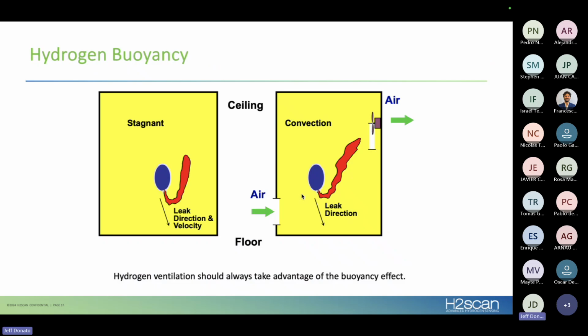We also have to watch where we place sensors. This is, I should say, not an application specific slide. With anything that's leaking hydrogen or creating hydrogen, we have to worry about the hydrogen buoyancy effect. Basically, this just means that hydrogen is fast moving. It's a very small molecule. So you want to make sure that the hydrogen system is put within the airstream.